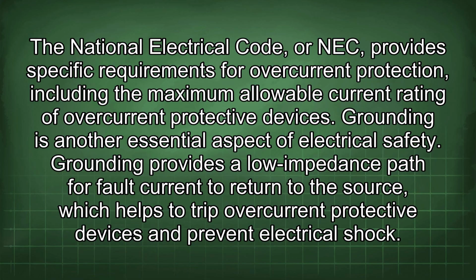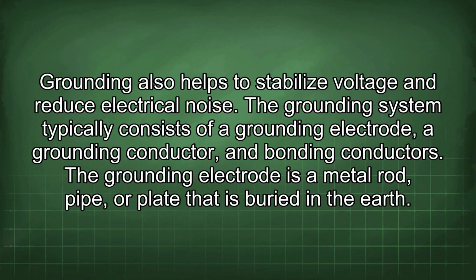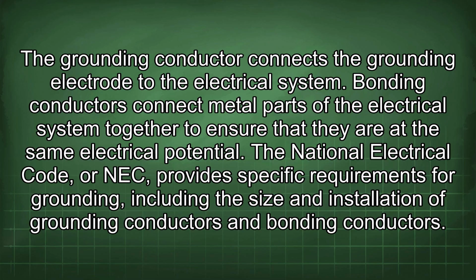Grounding is another essential aspect of electrical safety. Grounding provides a low impedance path for fault current to return to the source, which helps to trip overcurrent protective devices and prevent electrical shock. Grounding also helps to stabilize voltage and reduce electrical noise. A grounding system typically consists of a grounding electrode, a grounding conductor, and bonding conductors. The grounding electrode is a metal rod, pipe, or plate that is buried in the earth. The grounding conductor connects the grounding electrode to the electrical system. Bonding conductors connect metal parts of the electrical system together to ensure that they are at the same electrical potential.